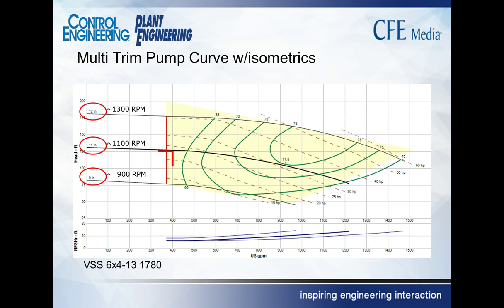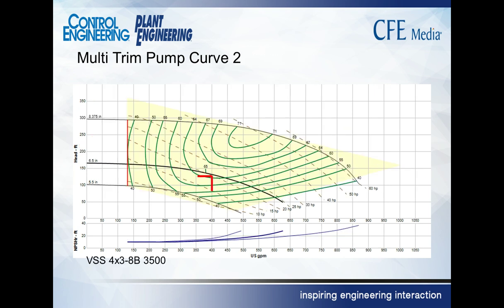It could be trimmed down as far as 9.5 inches. Alternately, we could change the speed of the pump to do about the same thing. And although these are not equivalent numbers, just to illustrate changes of speed, a change between 1,300 RPM and 1,100 RPM would be roughly equivalent to the change between a 13-inch impeller and an 11-inch impeller, and the same down to 9 inches. Here's a different pump.